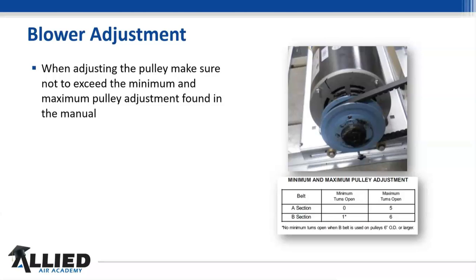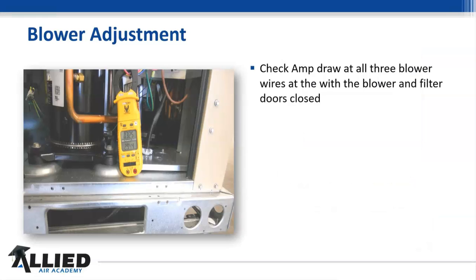So you got to be careful, because if you run that belt too low into that pulley, and it's an adjustable pulley, and it hits the threads on the actual pulley itself, that belt's going to prematurely fail. And you're going to have to keep going back and back. And it's going to be bad, especially we talked about last week, if you got a hospital setting or a restaurant setting and it goes down, it really affects how they operate. So really important not to take this little detail for granted on here, because it means the world to get this right. And then we're going to check the amp draw of the motor.